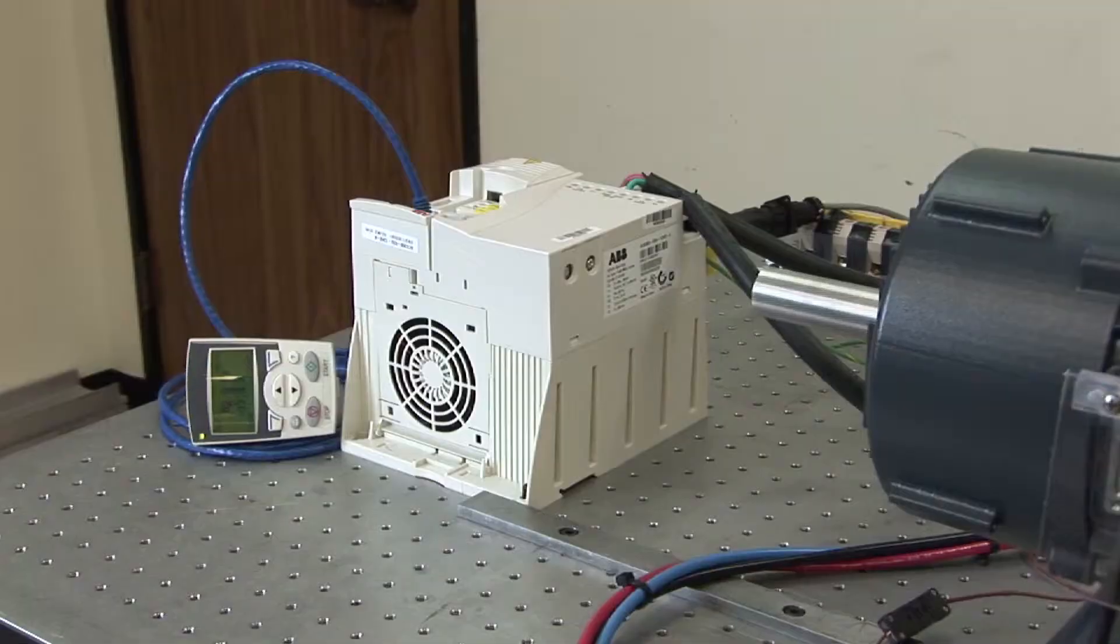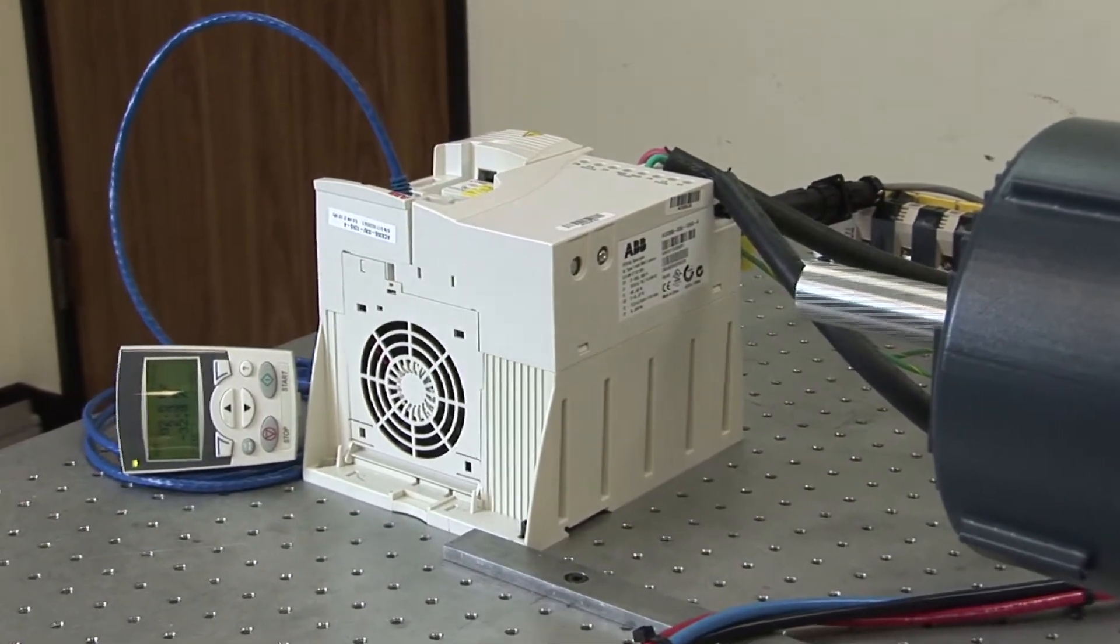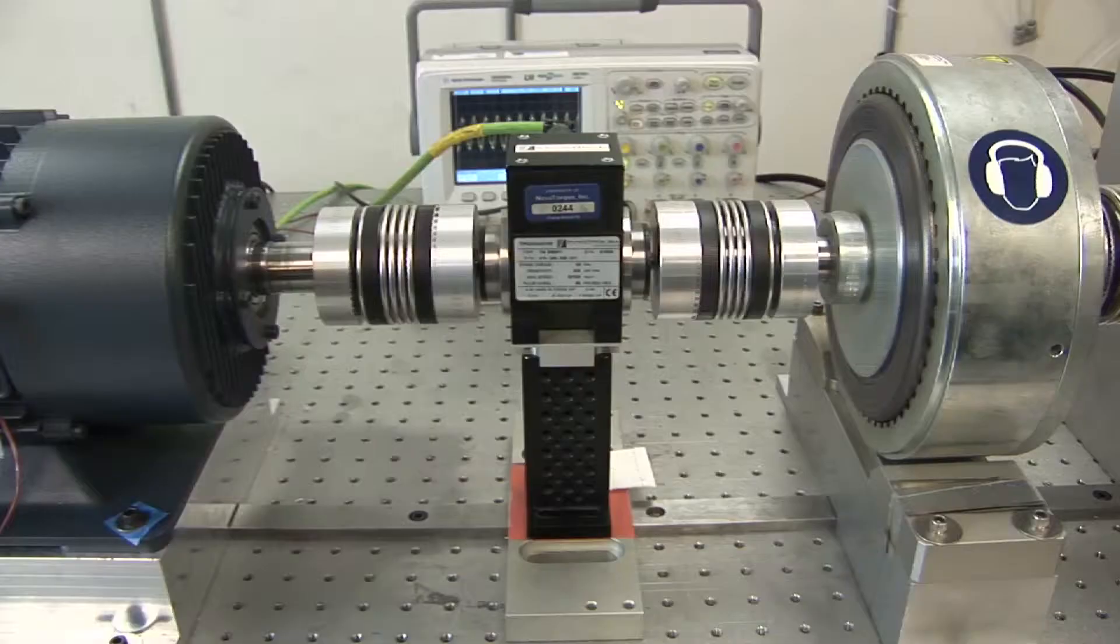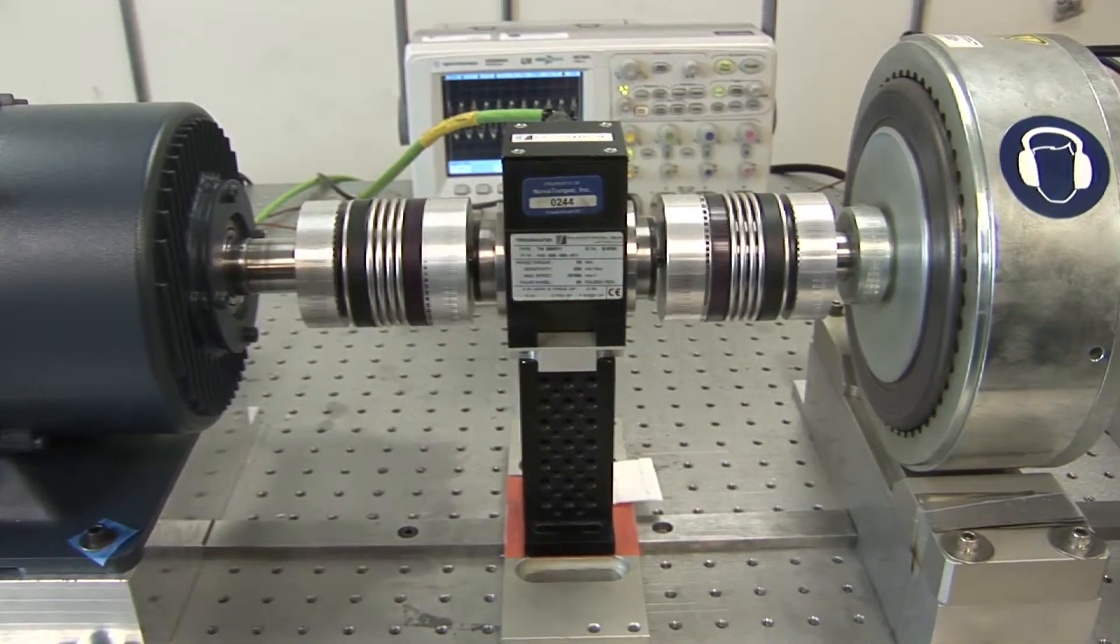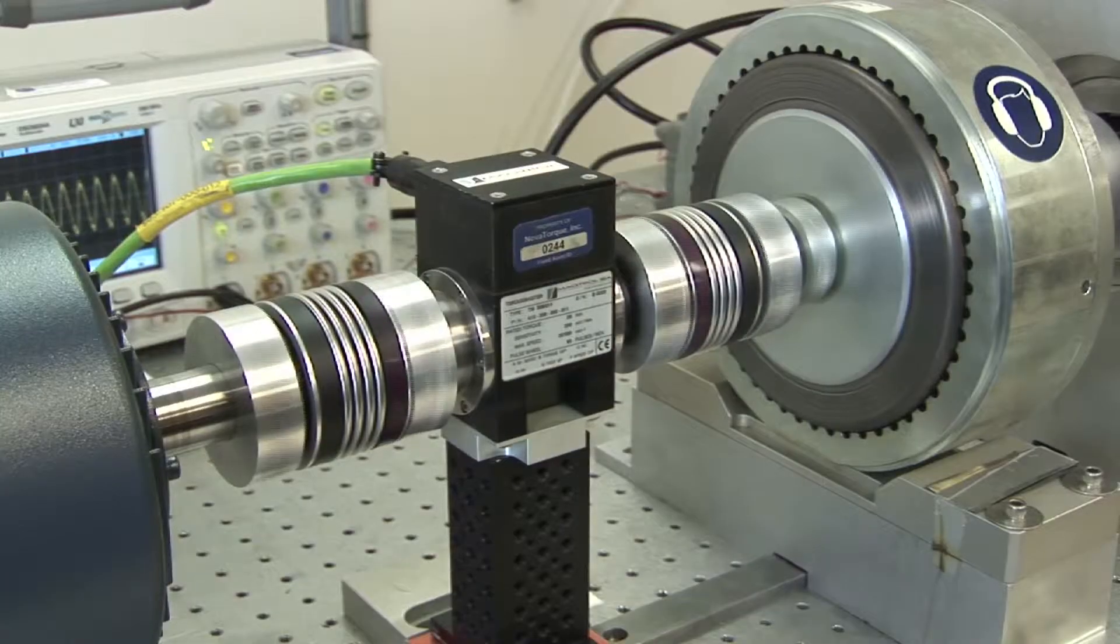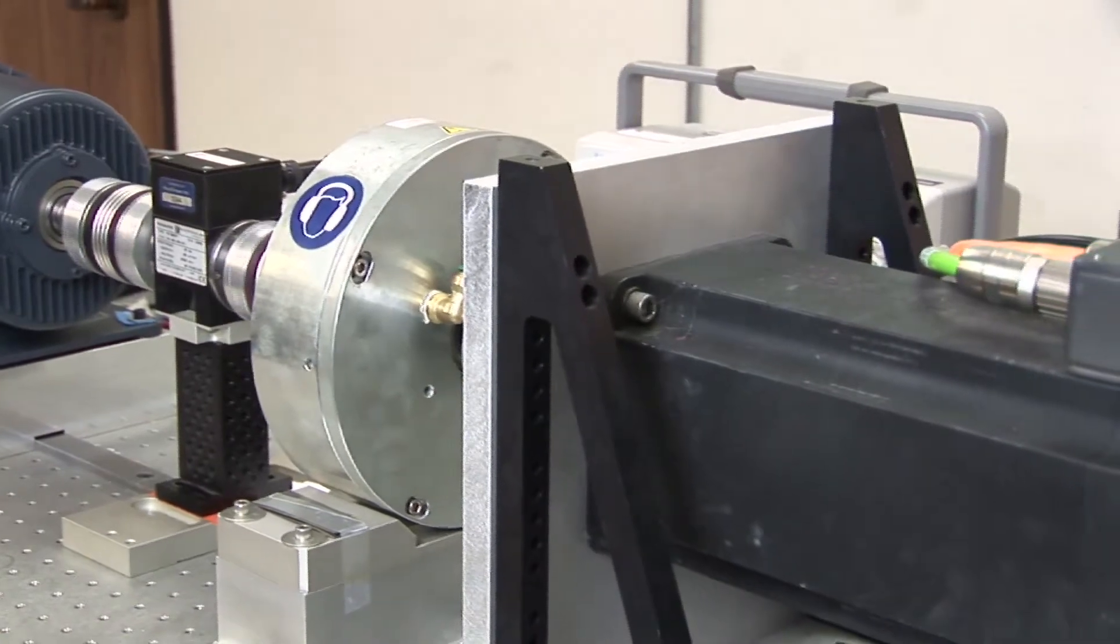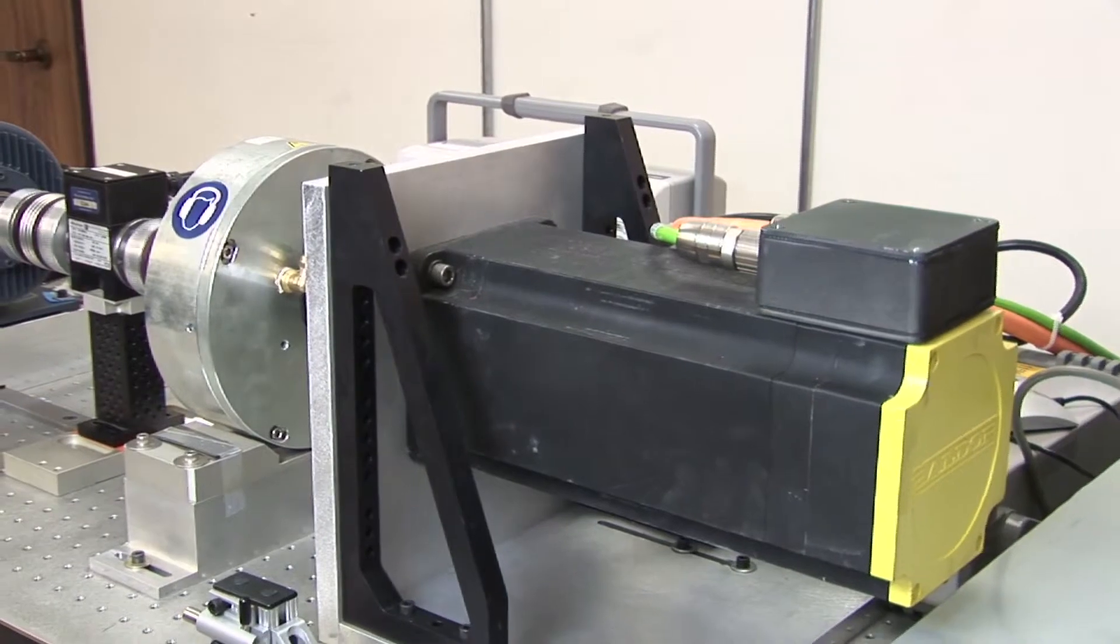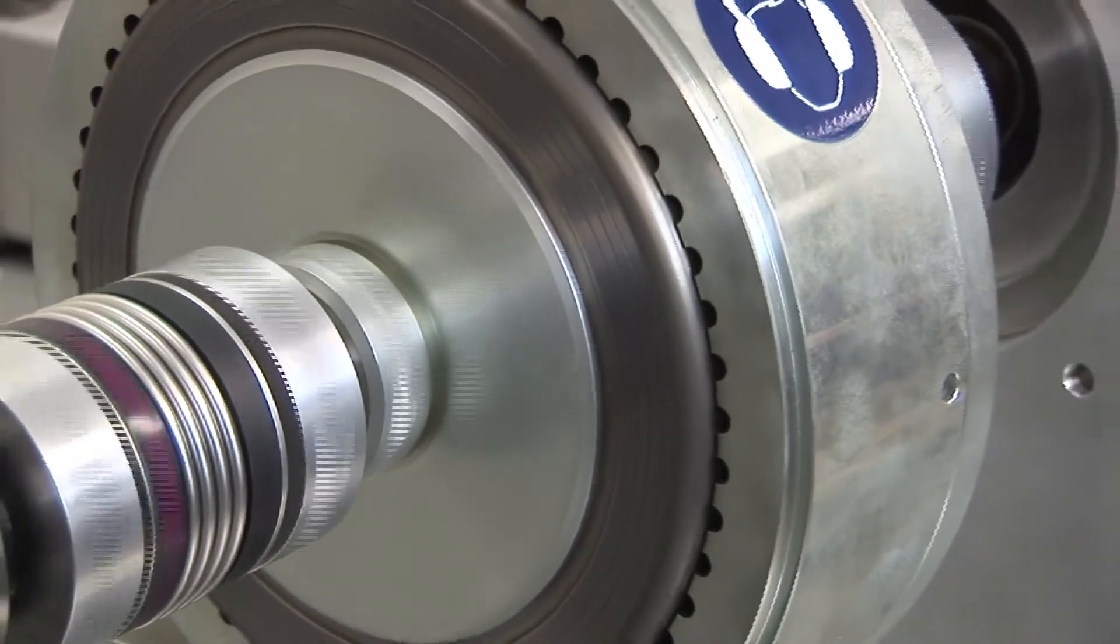The motor is operated using a commercially available variable frequency drive to control the operating speed. In this setup, the motor is driving a rotating torque transducer that measures the torque the motor is delivering, as well as speed. This is a dynamometer which provides the load to the test motor. We also have a hysteresis brake that is currently disengaged, which is used for low speed testing.